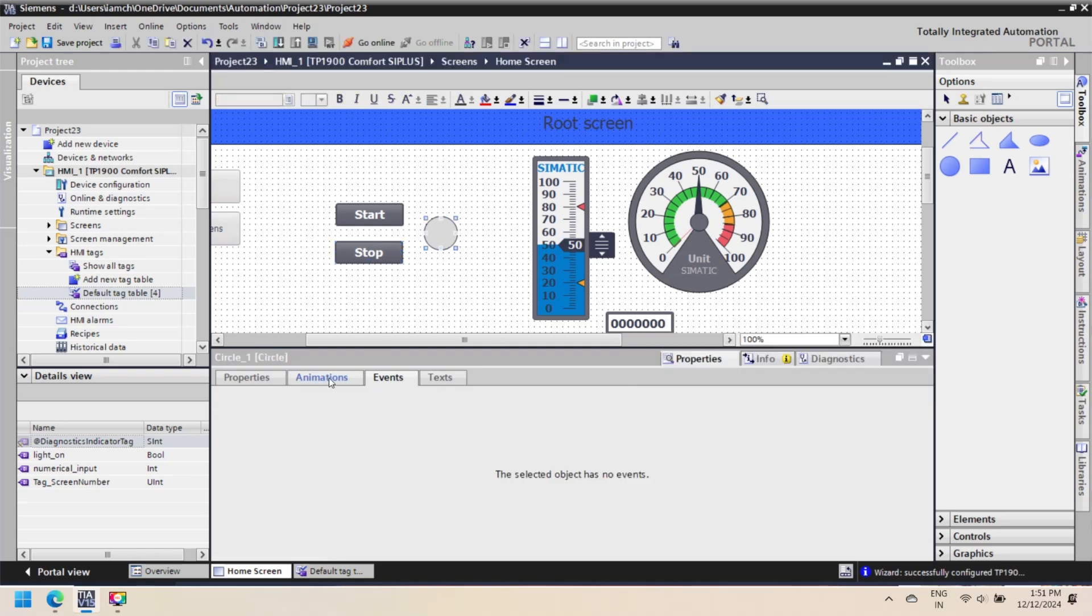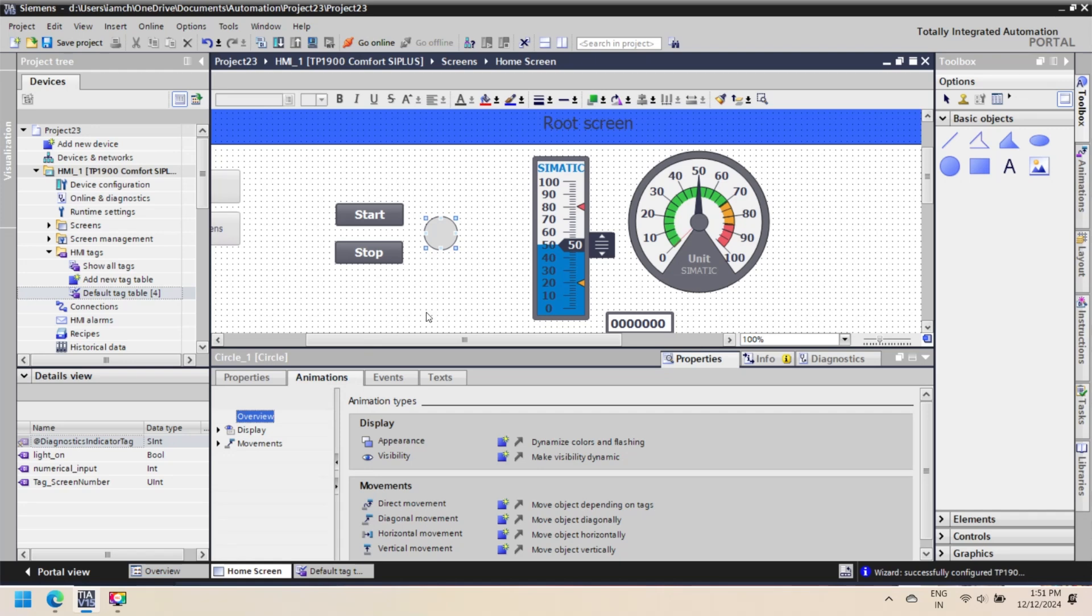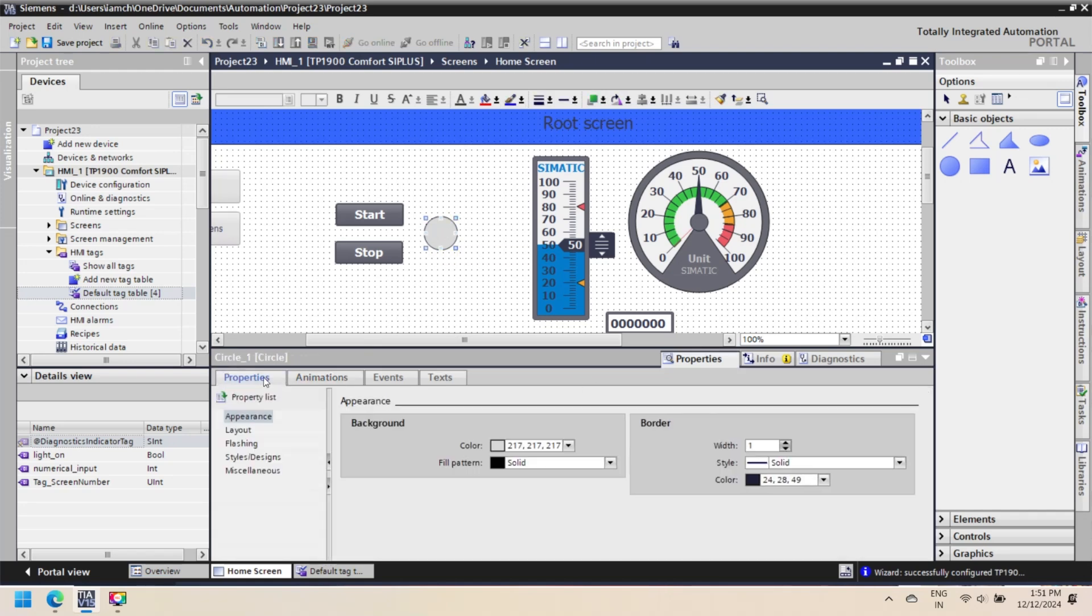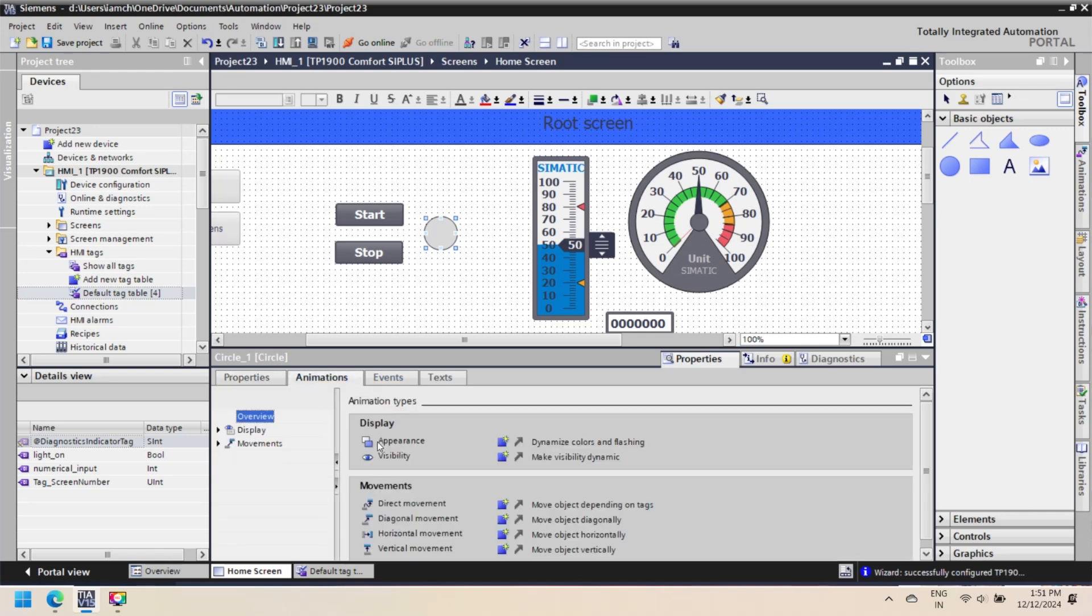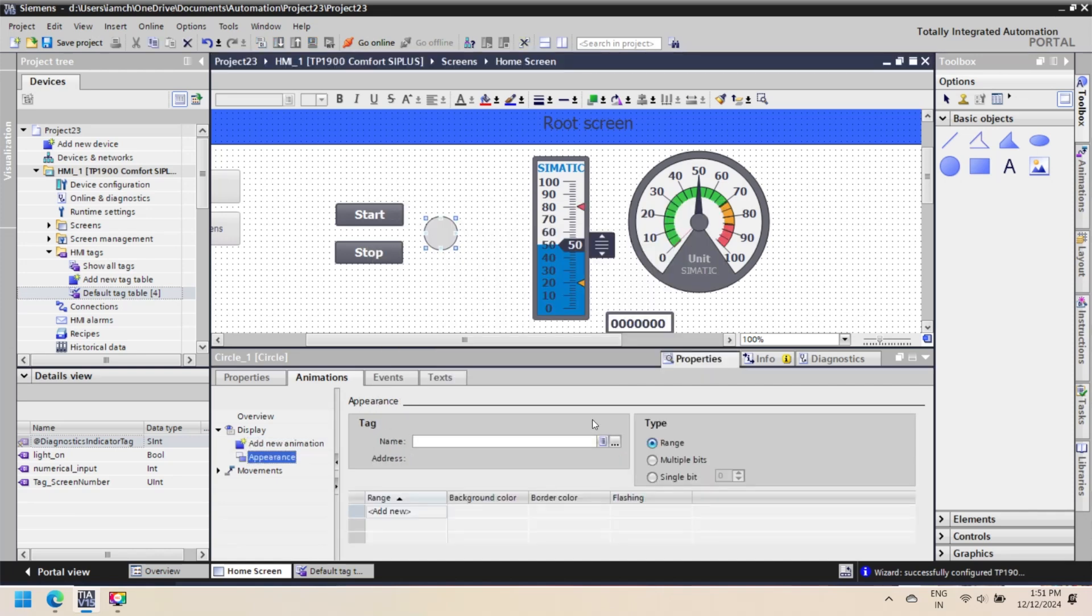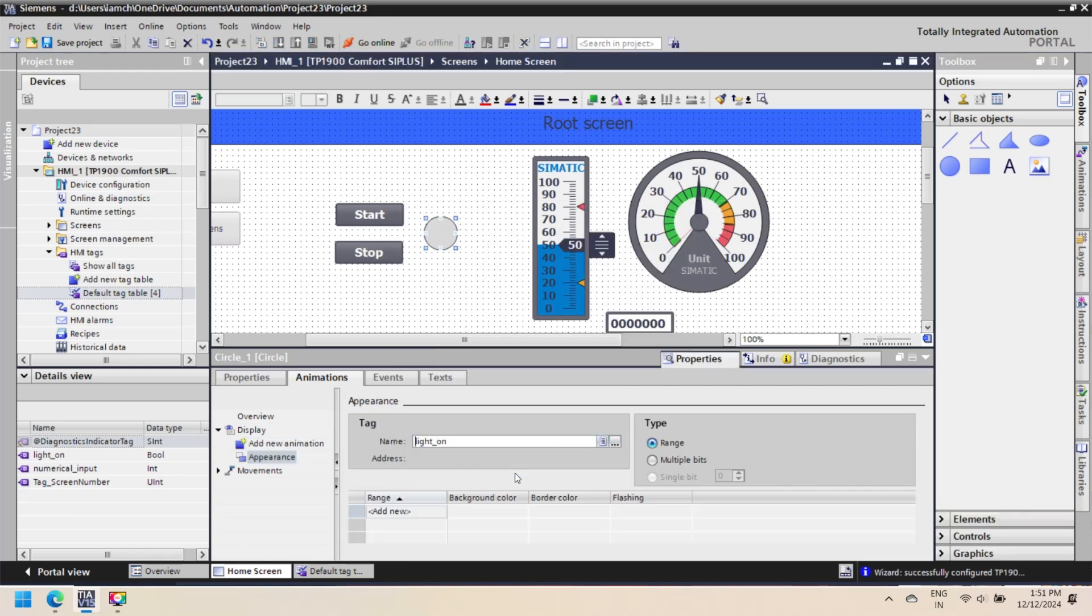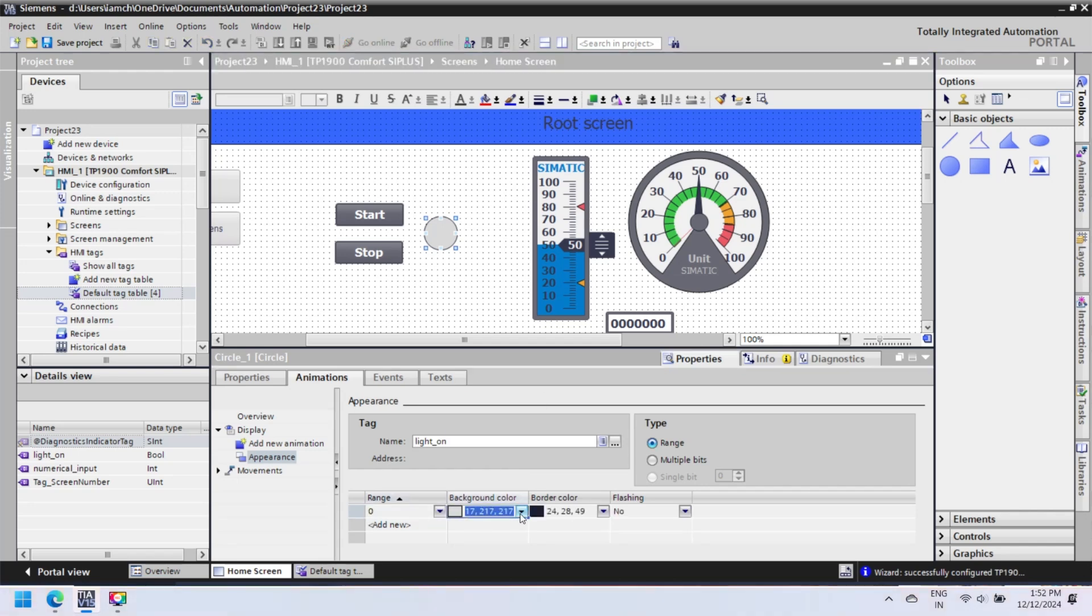Animation changes the background color, font color, visibility, movement, etc. when a selected component tag is changed to set value. Here we add animation of circle: when Start Button is pressed, then circle color changes to green, and if the Stop Button is pressed, then red color is set to circle. Set light_on tag for circle animation.